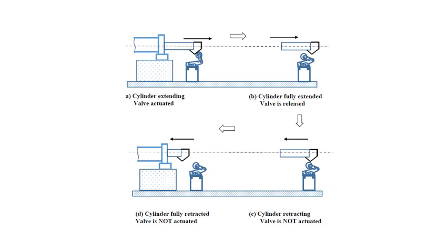So the retract signal is not going to be generated, only the forward one. This is useful when you want to count the components, how many components. Only while pushing out you need to count the component, while retracting you should not count. So with this kind of roller, while pushing, the limit switch generates the signal, while retracting back it won't generate the signal. So you can count how many times it is actuated or how many times it generated the signal in the counting systems.